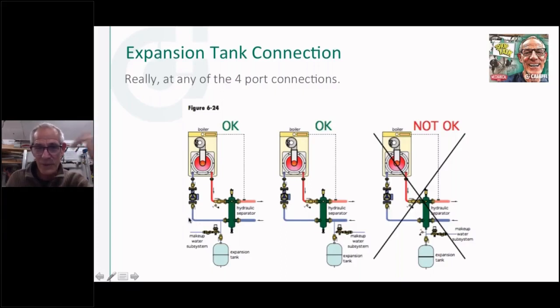So finally we got people thinking pumping away, and now we come back to, well, now they want us to pump back into the boiler. Now what? What do I do with my expansion tank? So yeah, you do want to pump away from your expansion tank all the time. So here we're going to add the delta P of this little circulator when it's running. It's going to show up as a positive pressure in this restrictive type of heat exchanger. So there's a good place right there, pumping away.